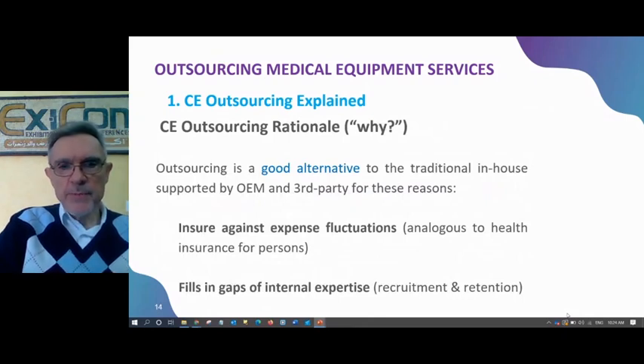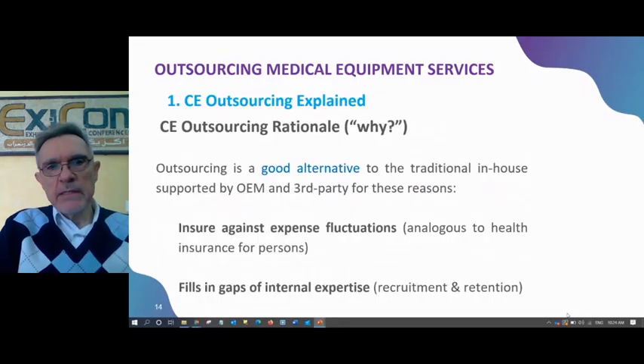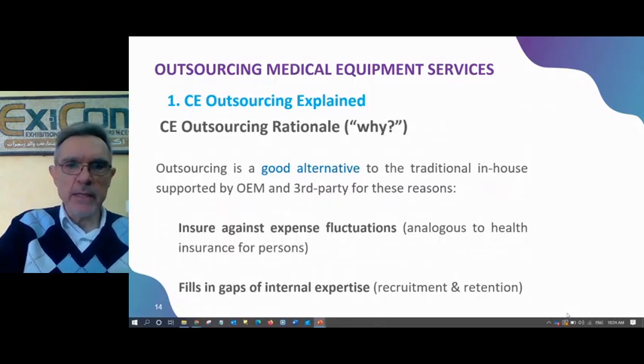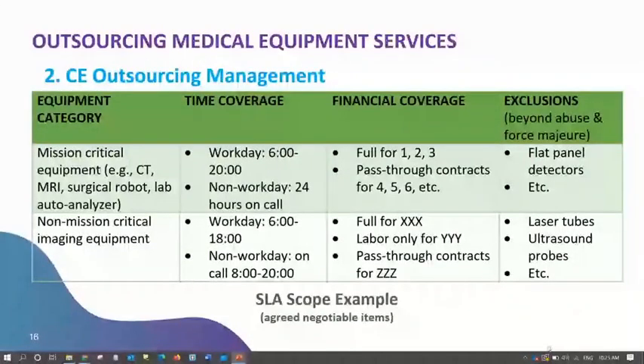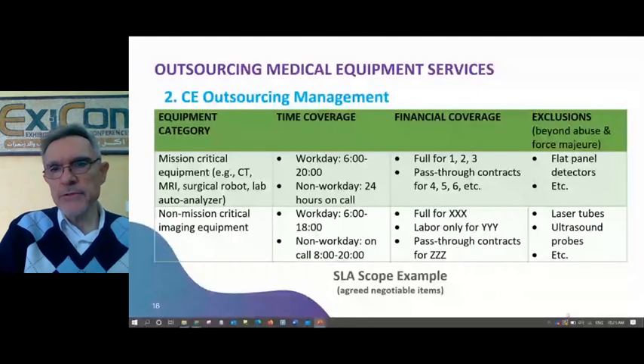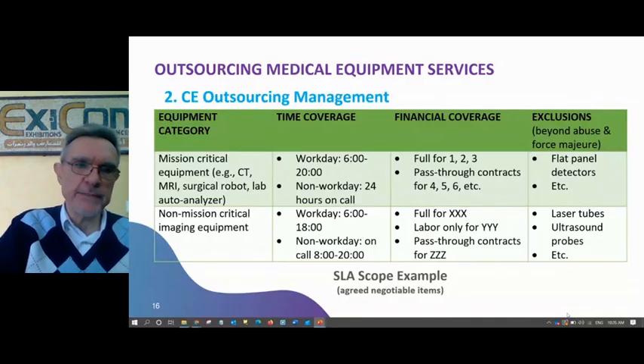Now, to do it properly, we need proper service level agreements. And let's take some examples. If we look at mission critical equipment like CT, MRI, surgical robot, lab, the time coverage can be, for example, from 6 till 20 and non-working days, 24 hours on call. And we can say that it would be full for items 1, 2, 3 and pass through for contracts for items 4, 5, 6. And surely there should be exclusions like the flat panel detectors, etc., which are beyond abuse and force majeure. And for non-mission critical, the timing would be different and the non-working days on call also different. And similarly, it can be full for items XXX, labor only for YYY, and pass through contracts for items ZZZ. And we have exclusions on the items.